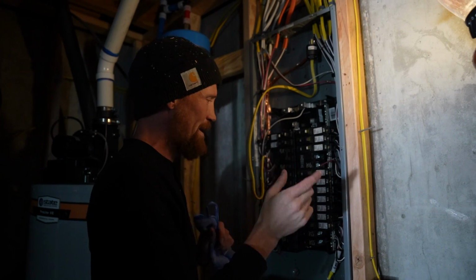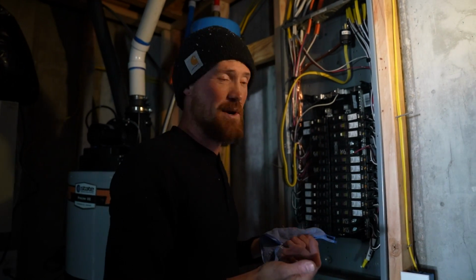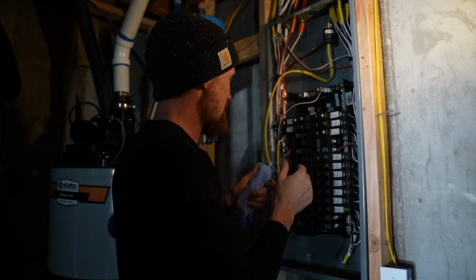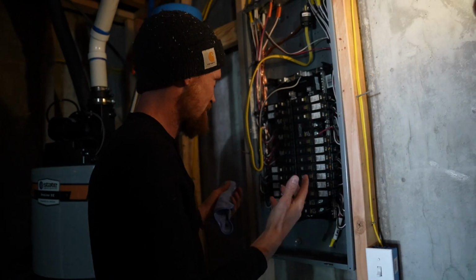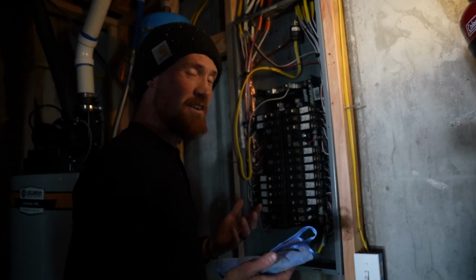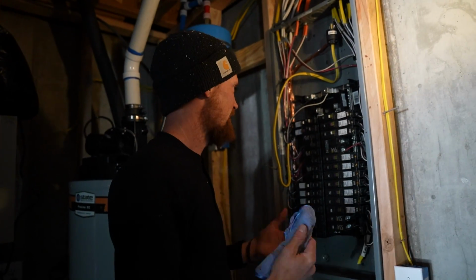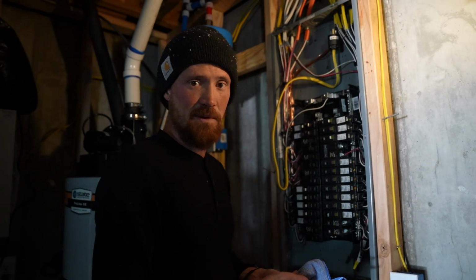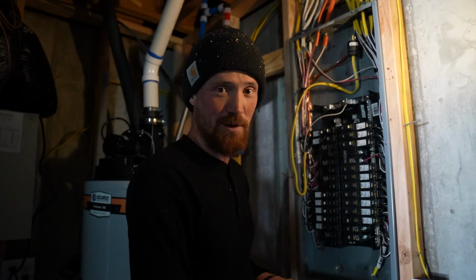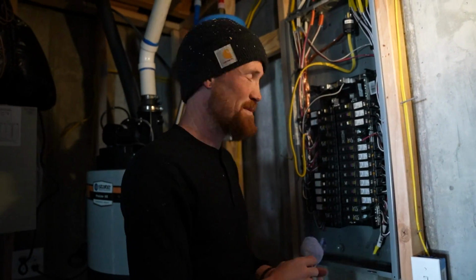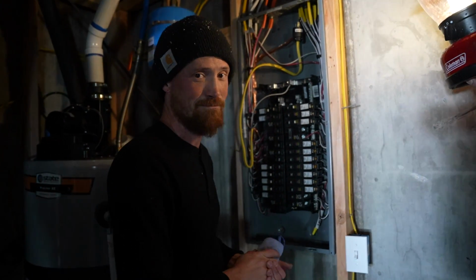Now when I try to energize the panel, the breaker keeps tripping because water is in here doing something, causing something to arc. I'm going to have to take off every single breaker and dry them all off, and I just hope we get to the bottom of it, because Brandon's already had to go reset the breaker down at the street like 12 times, and a 13th might kill him.